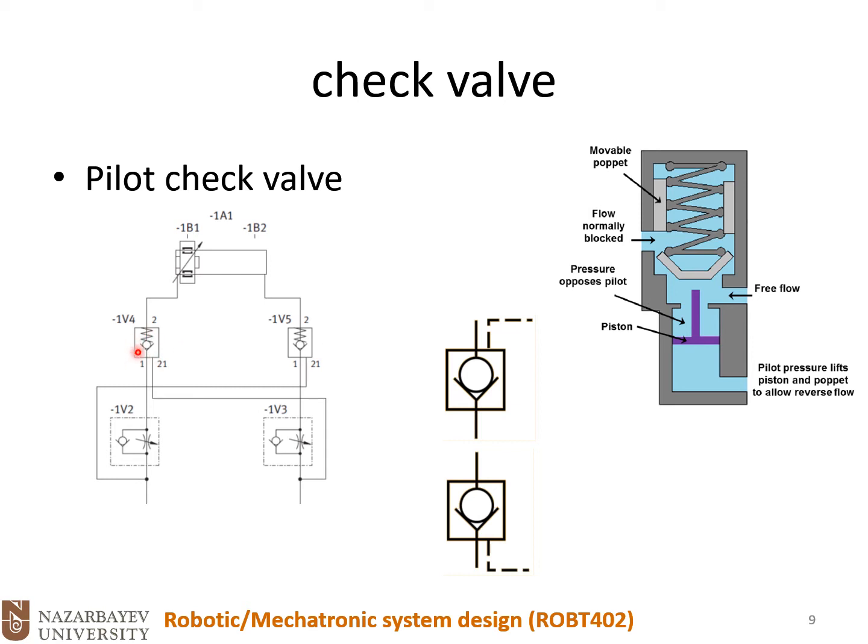The reason we have these non-return valves for the elevator is that the elevator has to lift weight, and it also needs to compensate its own weight. So we need to be careful of the air flow, because when we lift a heavy weight, or once the elevator weight is high enough, it could push the elevator back to its initial position, or it could create some vibrations.